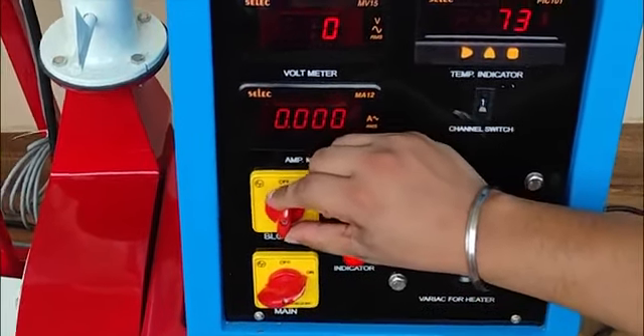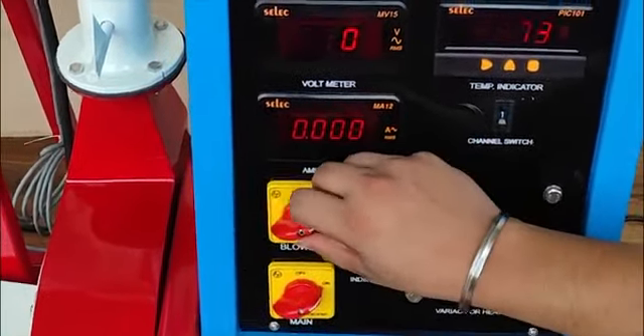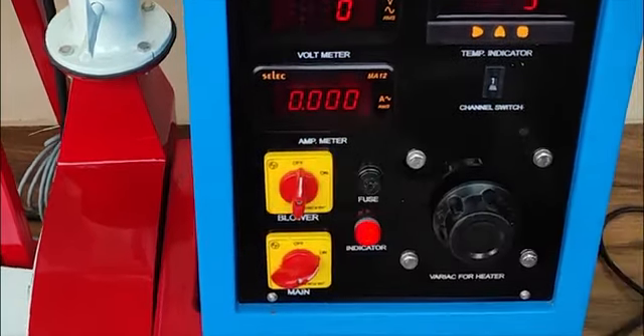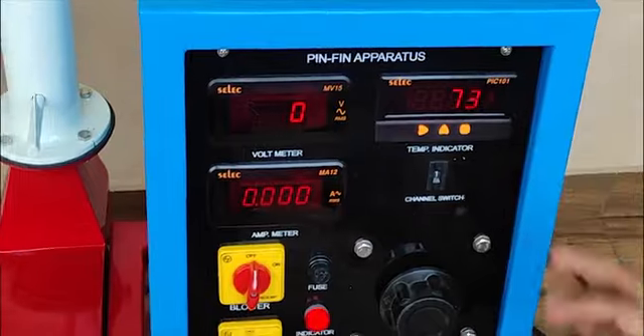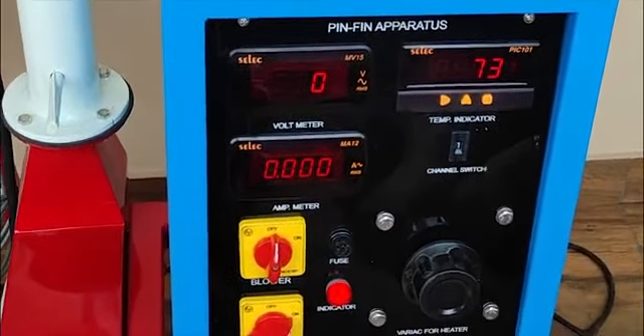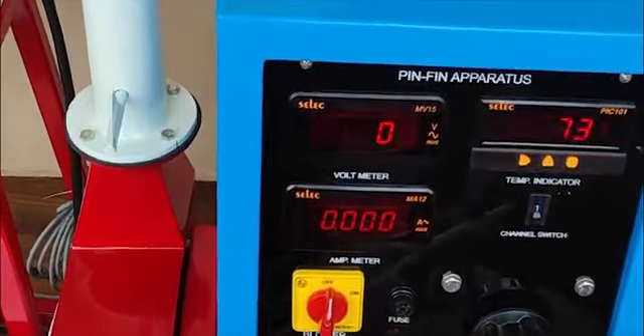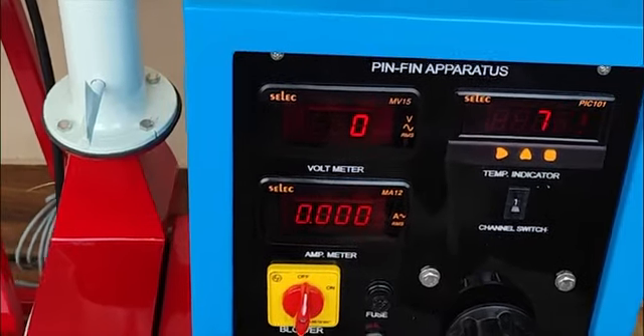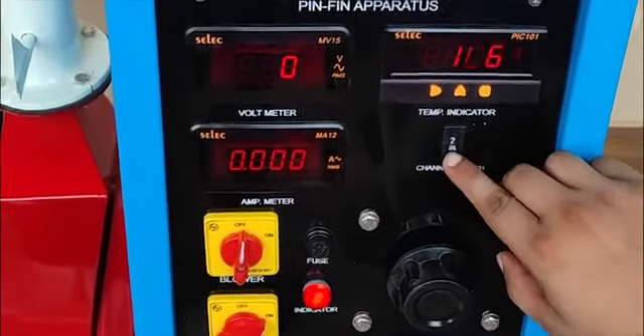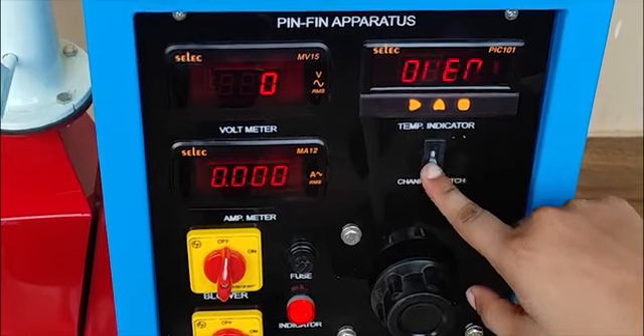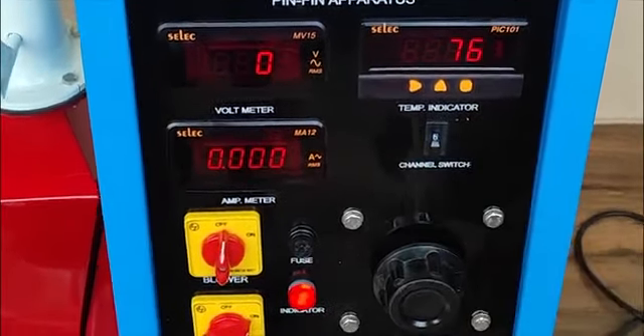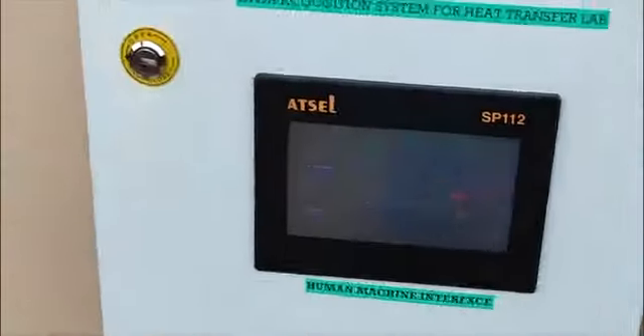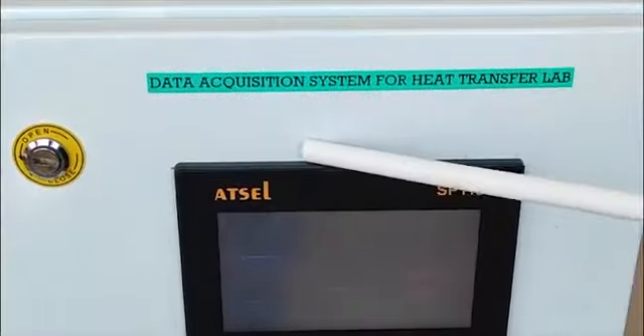We can start the blower of the motor. Thermocouple sensors are installed. Five on the pin and one around the field measuring the air temperature. So T1, T2, T3, T4, T5 and T6. Now our apparatus can be connected to this data acquisition system.